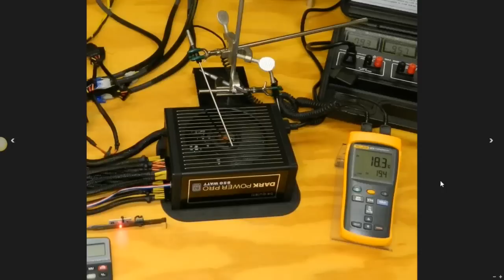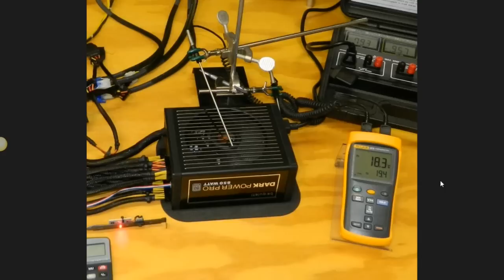Here's our next picture—a close-up of the actual power supply being tested. This shows the thermocouples and the differential temperature of the air going in versus the air coming out, 18.3 versus 19.4 there. That's our differential temperature, but again, normally we'd have the passive air ducts or hot box enclosure for the true testing.